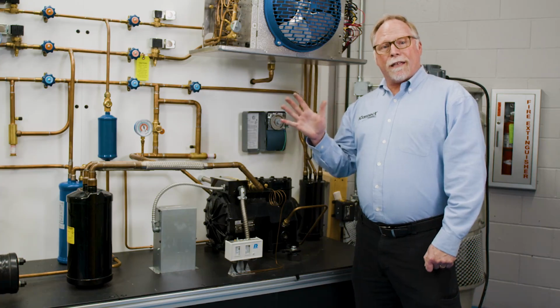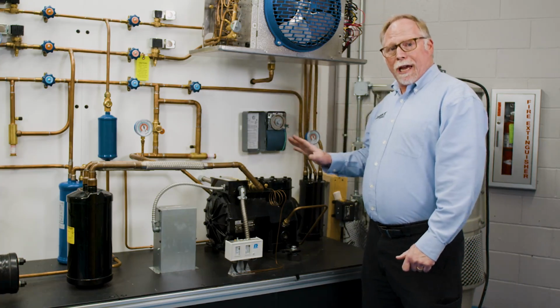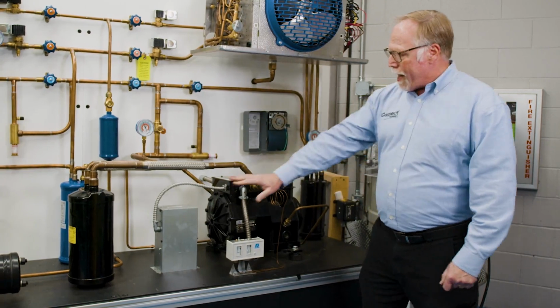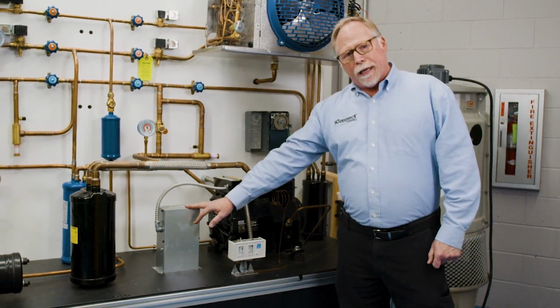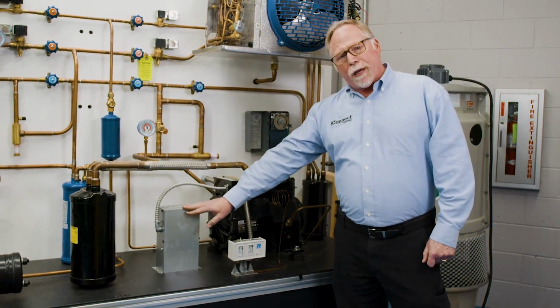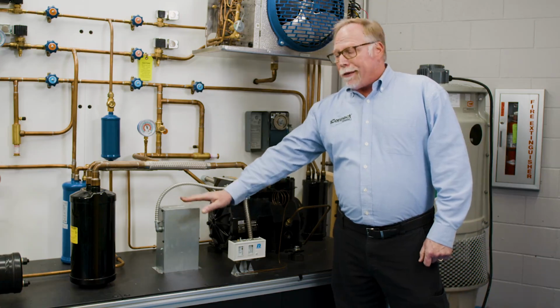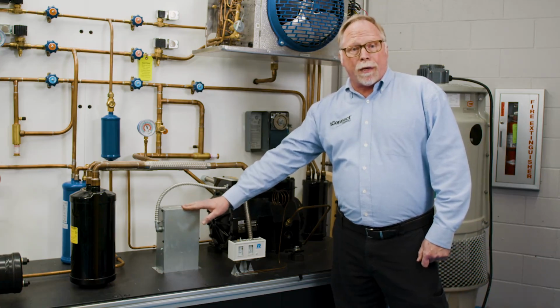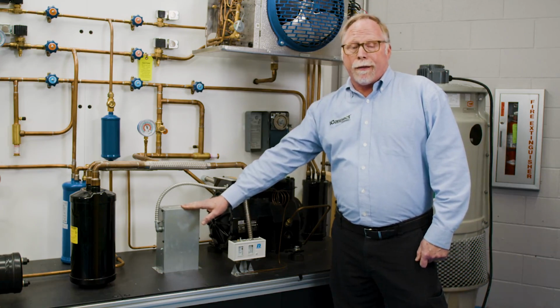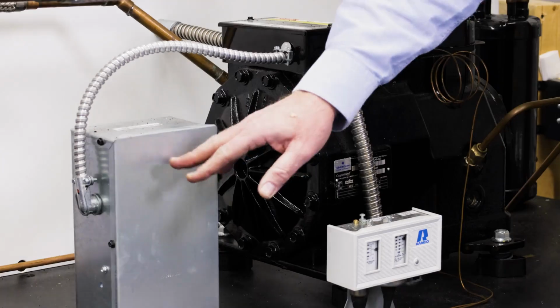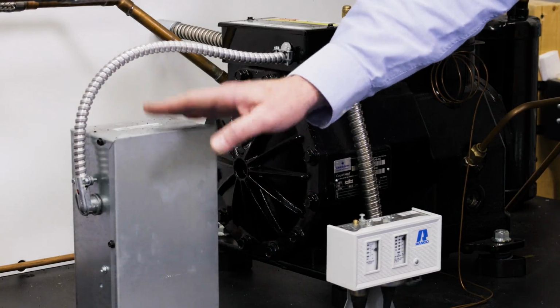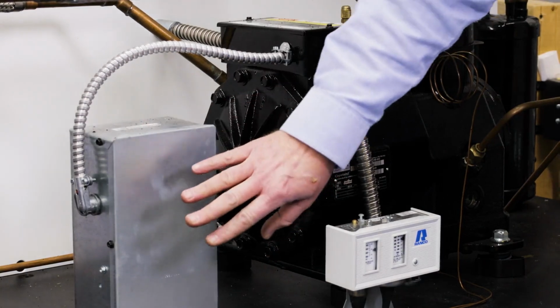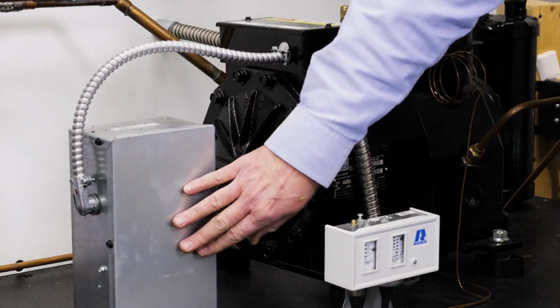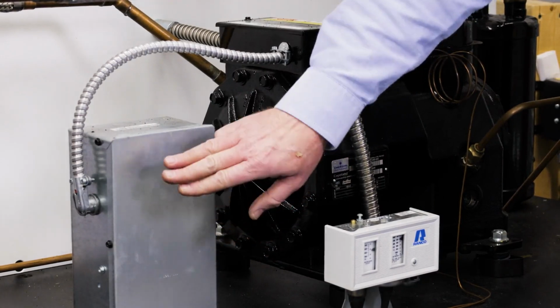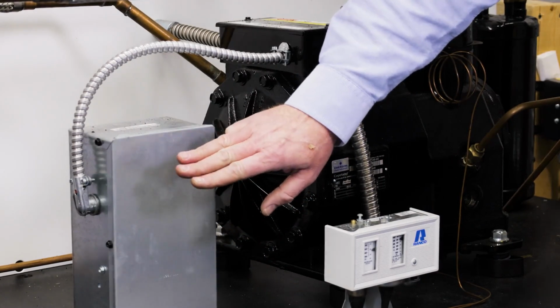The fifth lesson I would teach would be on the electrical side of this system. Here we have our hard start kit, with our relay and start capacitor. You could remove a wire to disable it and let them troubleshoot it from there. You can also swap out a good component with a failed one, since we keep boxes of those around, right? They could also measure the start capacitor and learn how to troubleshoot a start relay.